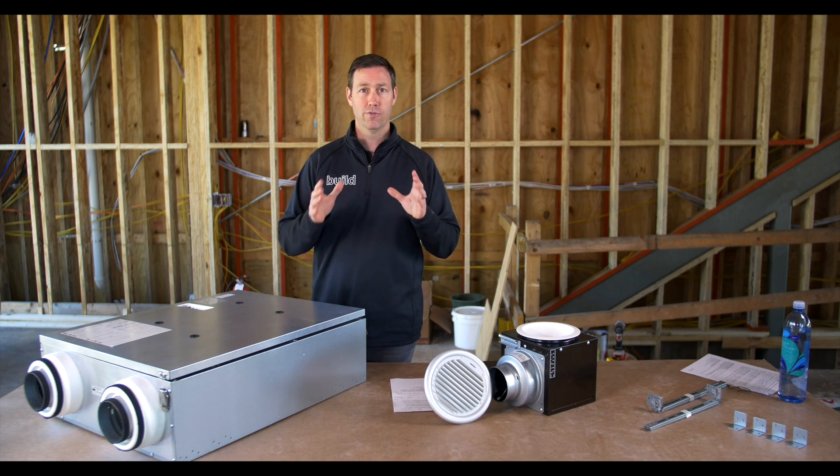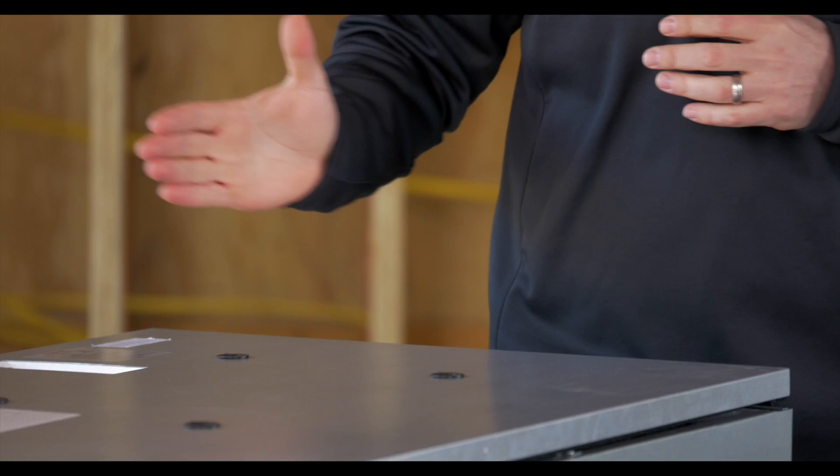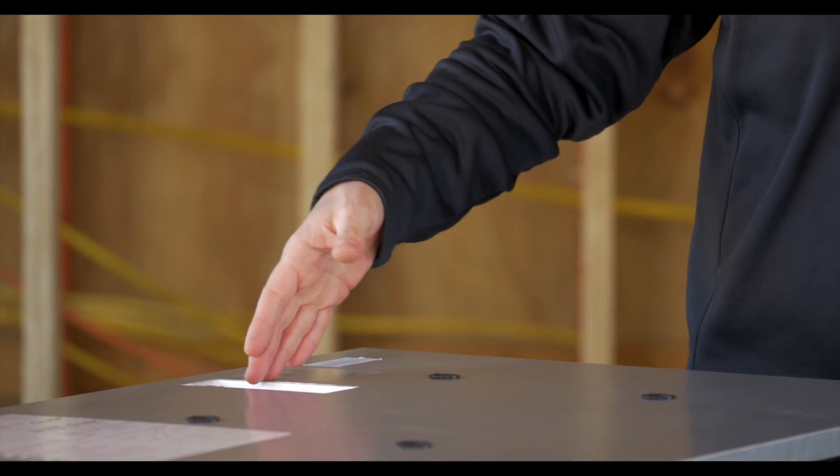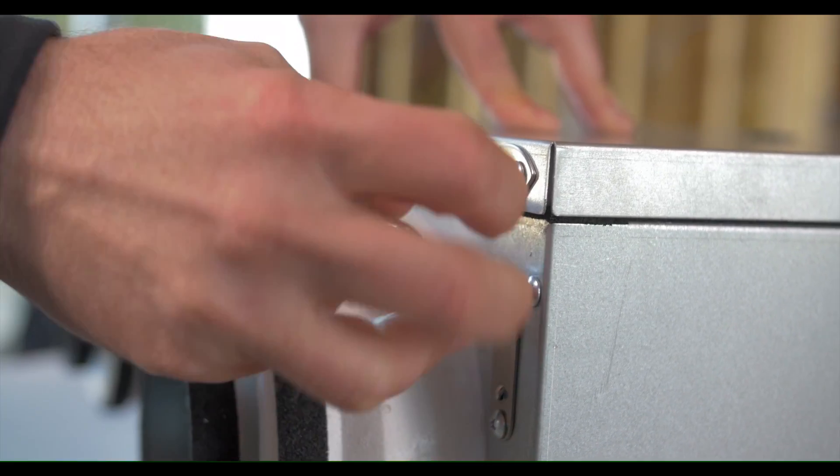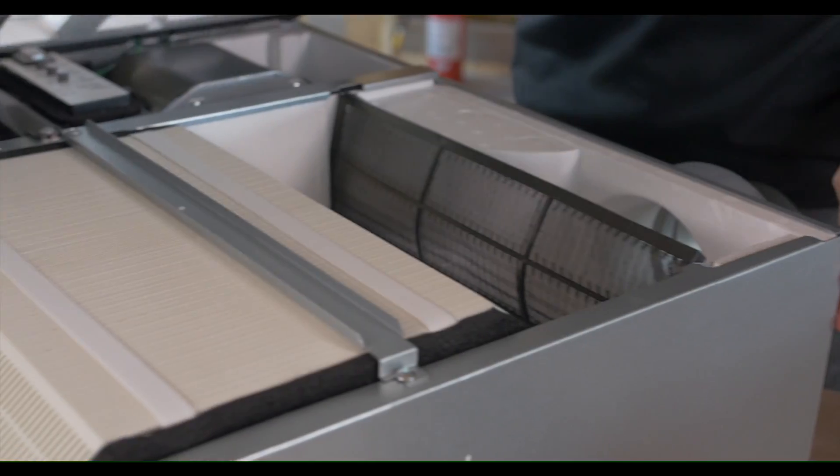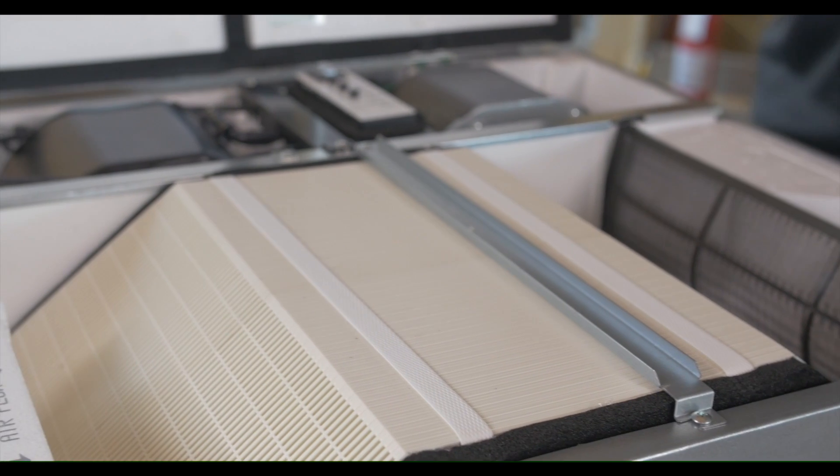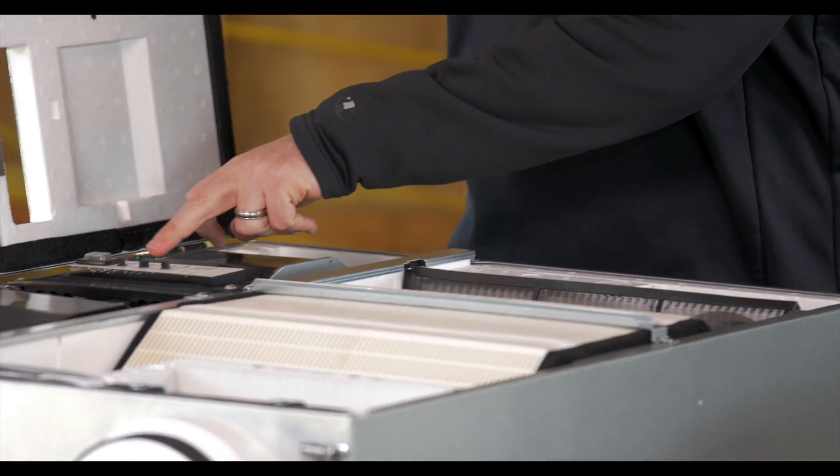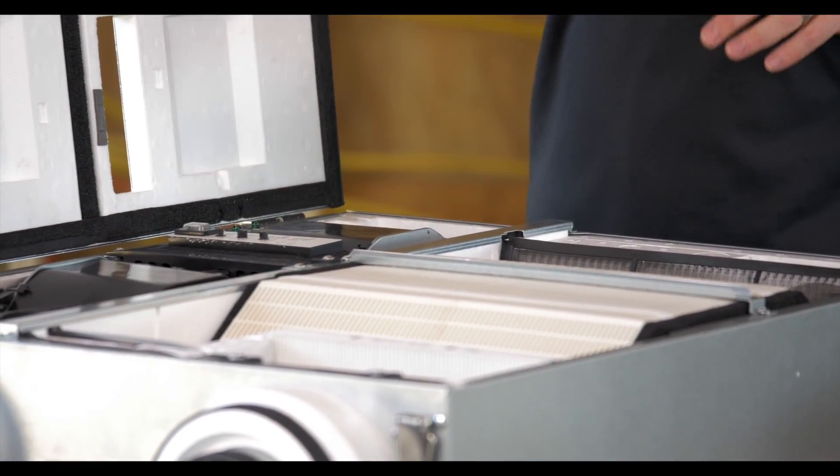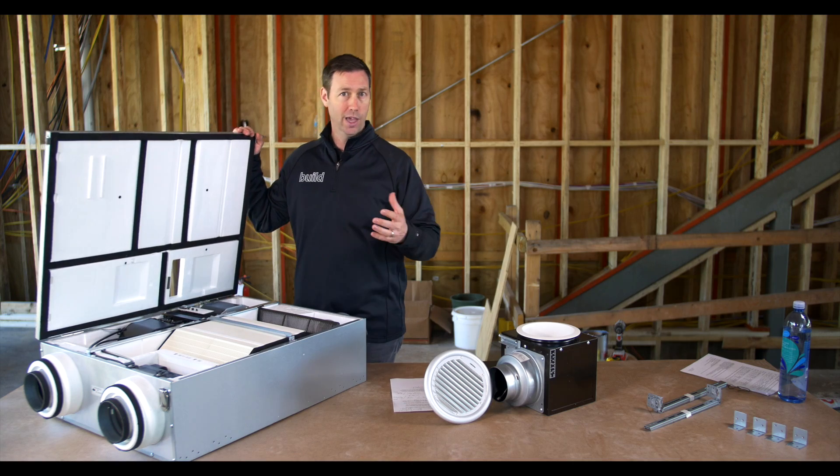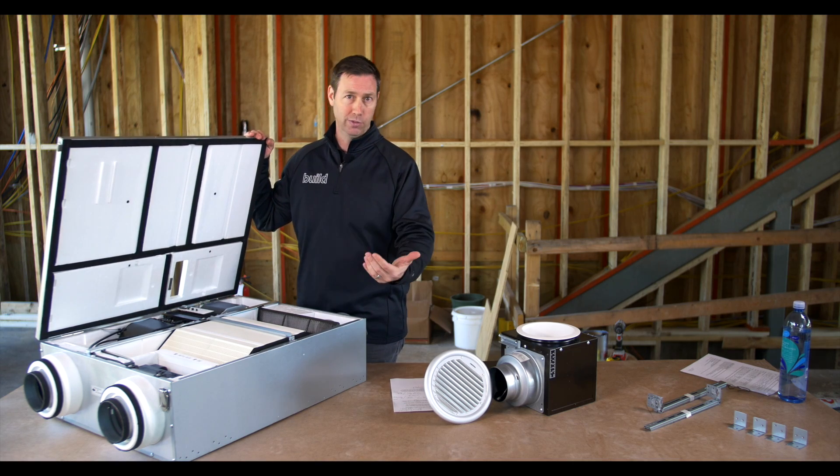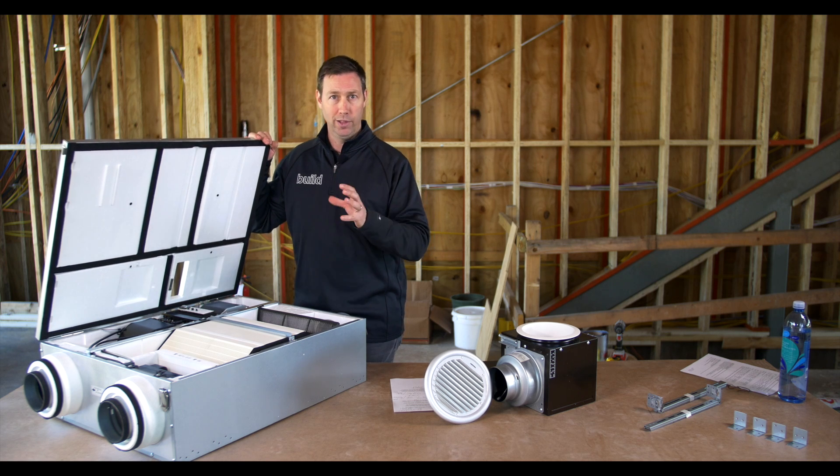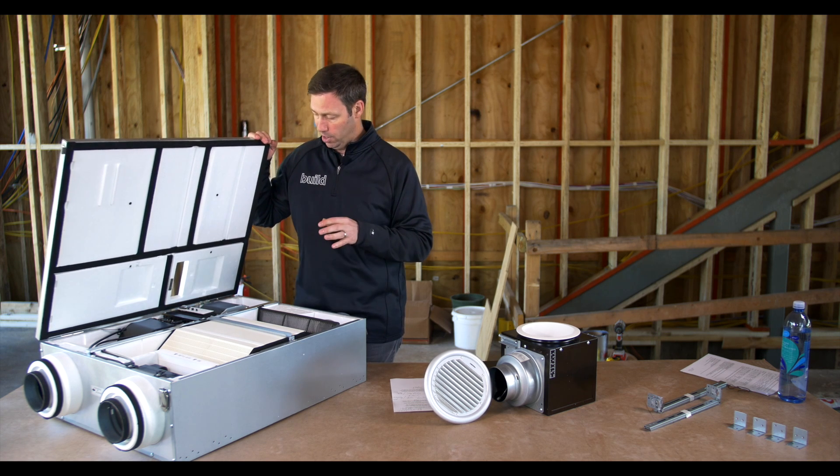Number one, it can vary its capacity. We can change this unit right up top here and change it from 50 CFM of supply up to 100 CFM in 10 CFM increments. And because it's got dual motors on here, we can change both the supply air and the exhaust air differentially. I like that because now I can decide do I want to positively pressurize, negatively pressurize or balance that air in my house.